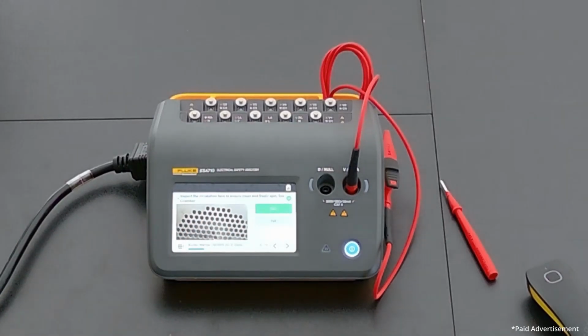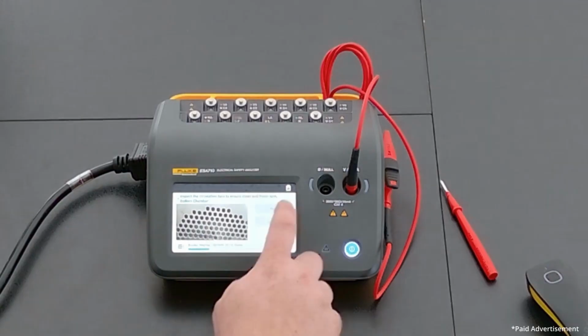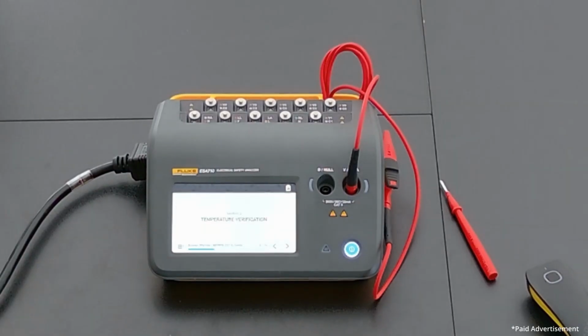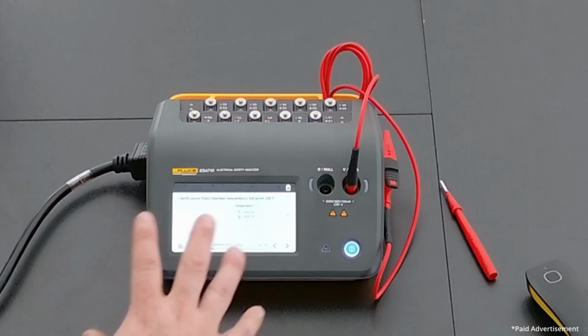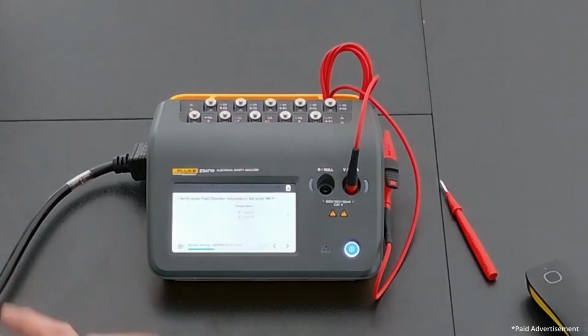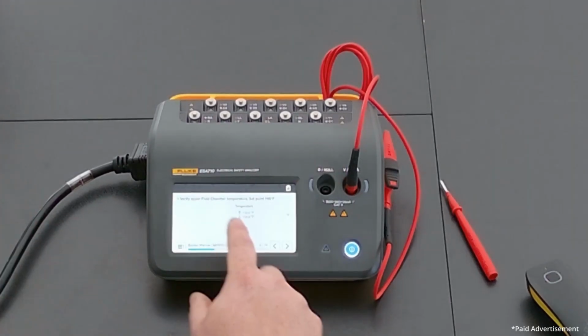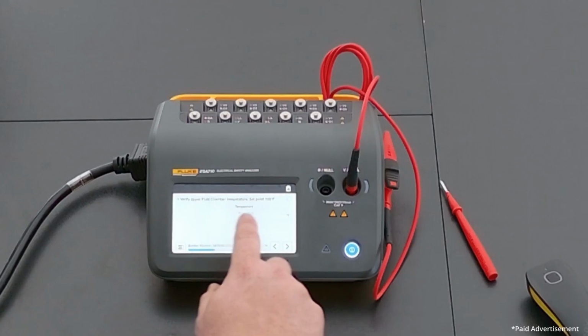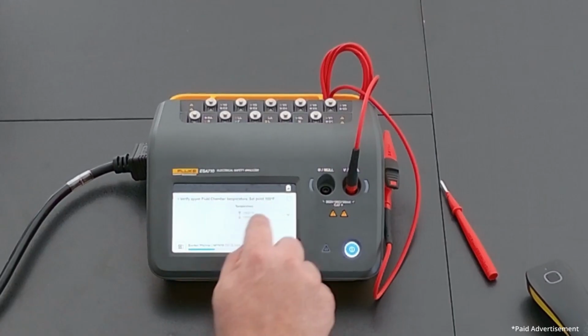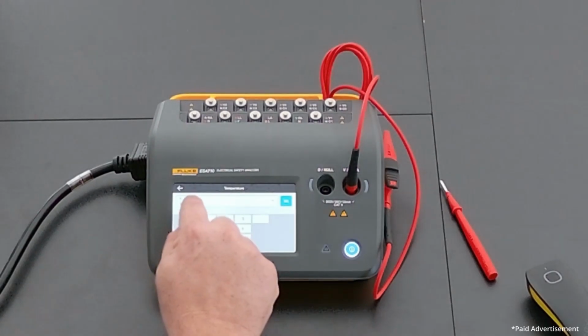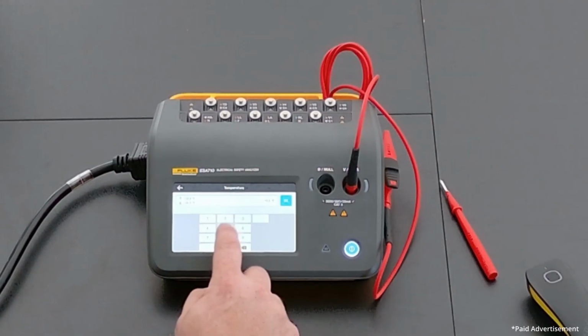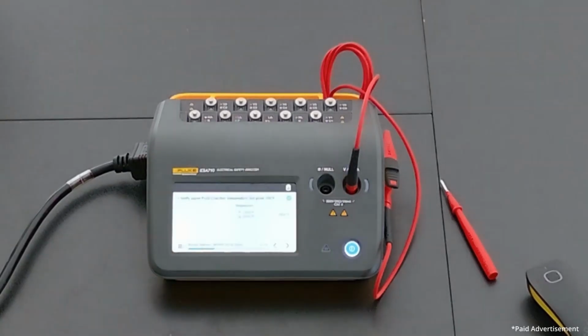So I can say yes, my fan's clean, and my bottom chamber fan's clean. Now for temperature verifications. With a Fluke 52 II thermometer, I can put it into my upper fluid chamber and take a temperature reading. The set point should be 105. You'll see right here on the screen that my tolerances are pre-built in. So I take my measurement, say 105, and hit OK, and because it's between the two tolerances, it passes.